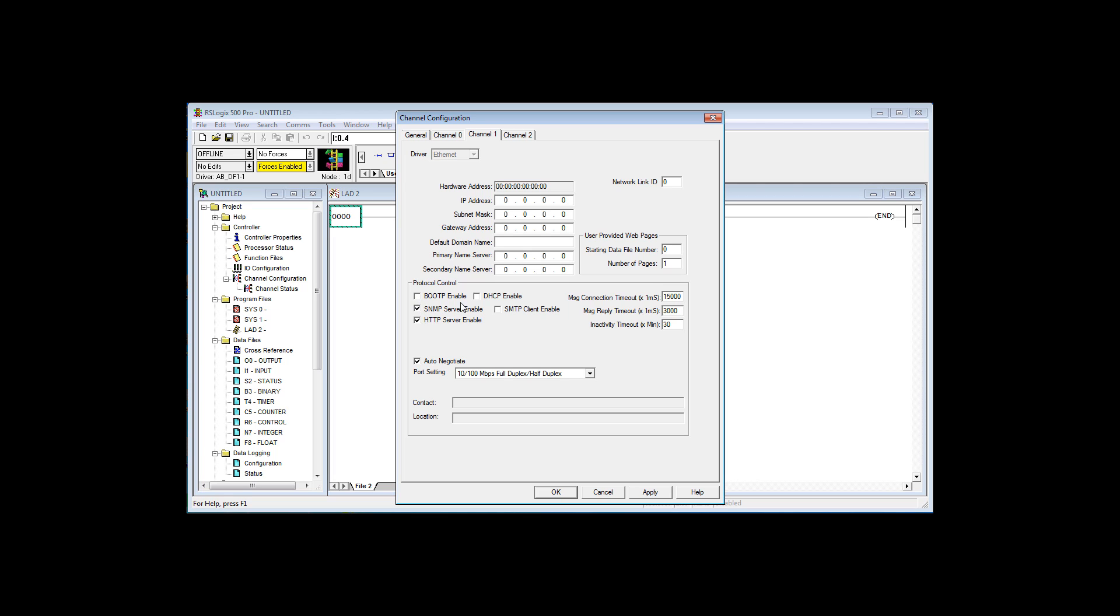BOOTP and DHCP, Dynamic Host Configuration Protocol, they're very similar. The difference is, with BOOTP, you need a BOOTP server, and it has to have a fixed IP address associated with that MAC ID, or that hardware address. With DHCP, if you select that, then the controller at whatever MAC hardware address you have, is going to send out a message onto the network, to the server, asking for an IP address. The server will then lease that address to the controller temporarily. We prefer fixed IP addresses, so we're not using BOOTP or DHCP.